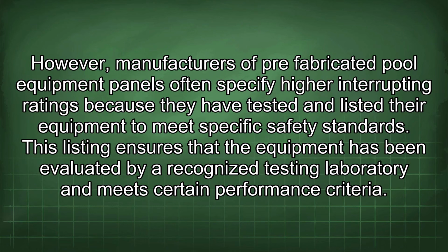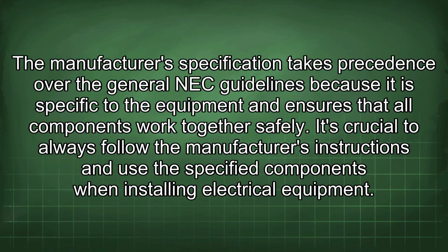However, manufacturers of prefabricated pool equipment panels often specify higher interrupting ratings because they have tested and listed their equipment to meet specific safety standards. This listing ensures that the equipment has been evaluated by a recognized testing laboratory and meets certain performance criteria. The manufacturer's specification takes precedence over the general NEC guidelines because it is specific to the equipment and ensures that all components work together safely.